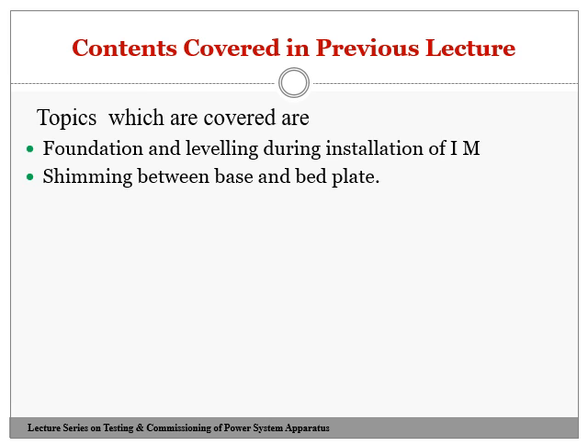Therefore, this foundation, the concrete mixture, should be done according to the standard provided by the Indian Standard. Afterwards we came to know about shimming, the meaning of a shim. It is a steel or metal piece provided between the base plate and the bed plate of any machine to raise or lower the machine height so that proper alignment can be done if you are going to couple the motor and the generator set. Then we saw that the bed plate provided for a motor generator set may be one complete part, or it may be separate for the motor as well as for the generator, which you have seen in the previous class.